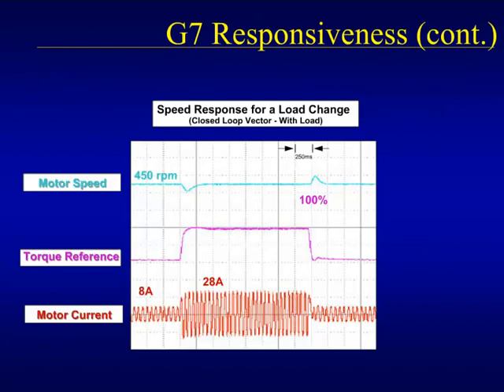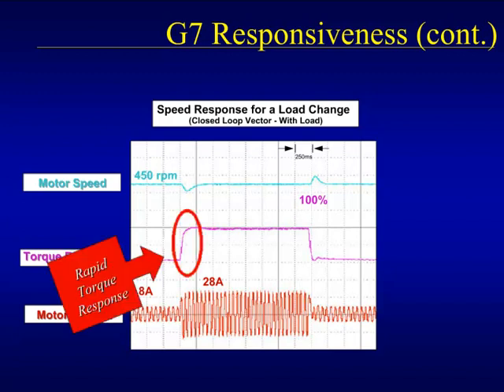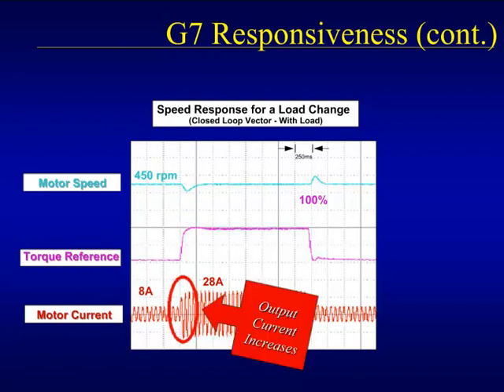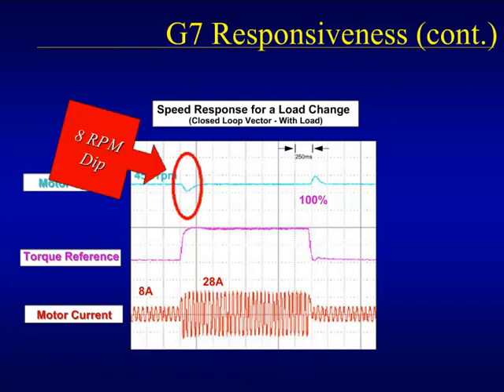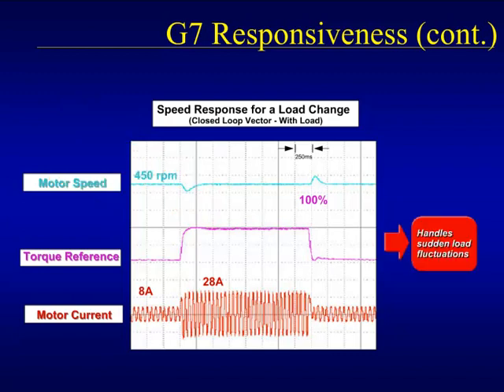This slide shows how the G7 responds to a shock loading situation. The scope trace shown details how the load suddenly changes and the G7 responds with a rapid change in torque reference and a motor current that more than triples. The end effect of the shock load is a small dip in motor speed that never exceeds 8 RPMs and is over in approximately 0.3 of a second. Though not at servo response capabilities, the G7 speed response closes the gap between the AC drives and the servo drives.